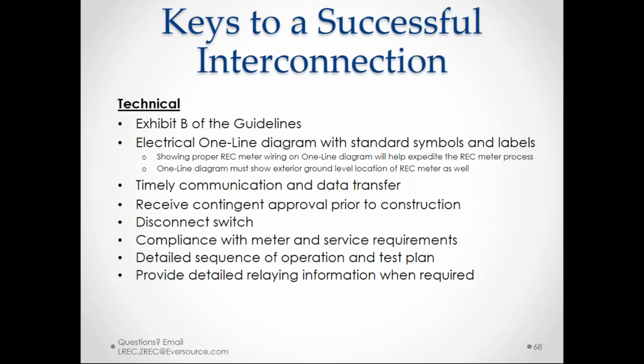And obviously, in terms of dovetailing this with the ZREC process, I did state that interconnection is a separate but parallel process with the ZREC process. And typically, most of our interconnections that are received tend to already have a ZREC contract award the majority of the time. So you do yourself a favor by making sure that the one line already has the ZREC meter identified clearly, and as well has the requirements that I'll discuss in the next section where I'm covering meter engineering. Then we'll have the required details for 3-line details of REC metering drawn correctly, as well as identifying the location on the site plan.